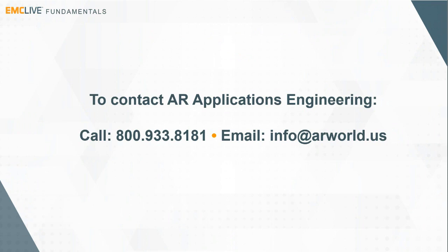As you can see, the benefit of multi-tone testing is significant, and with EMCware, this testing is fully automated. AR RF microwave has been on the forefront of EMC multi-tone methodology. The adoption of multi-tone into IEC 61000-4-3 is evidence that this represents the state-of-the-art of EMC testing technology. Please contact AR Applications for a system that meets your particular unique requirements.